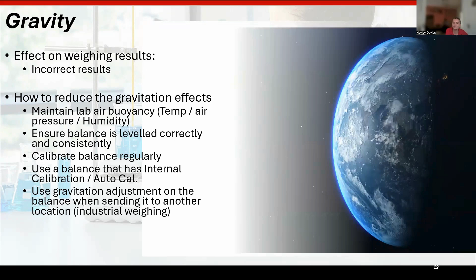And this is really mainly for some of your higher end, your semi-micro and micro balances. Gravity can be a factor. If you're moving it to a different location, the gravitational pull is different all around the country. If you're moving it from one lab to another in the school, the gravitational pull is not going to have much of an effect. But small differences in local gravity can lead to incorrect results. So to avoid it, make sure your balance is always level, calibrate it regularly, and use the built-in gravity adjustment function if that is available on your balance, particularly for any industrial or portable weighing.